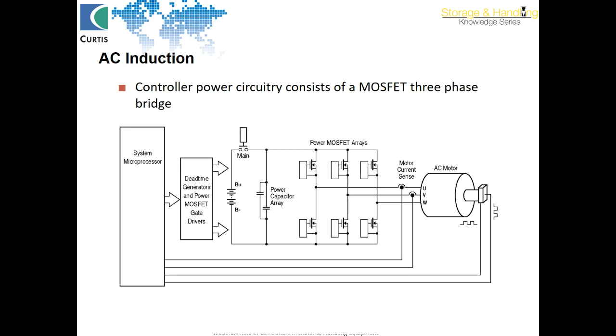Then you have a battery and the main contactor, which is an electromechanical switchgear. Then you have an internal filter capacitor bank, named the power capacitor array. Then the 6 MOSFET bridge, the 3-phase output, and the current sensors fitted on 2 phases. The third phase does not require a current sensor because the current can be estimated from the 2 phases. And the motor should have a quadrature encoder to give the position feedback, RPM, and direction of rotation of the shaft. You can see two square waveforms coming back from the encoder, which are 90 degrees phase apart.